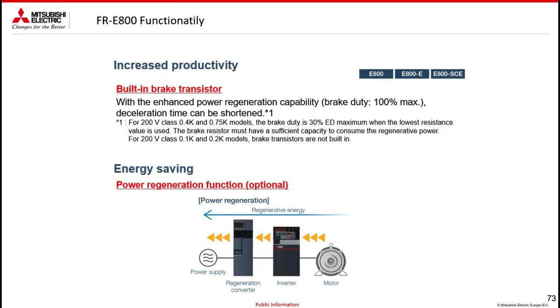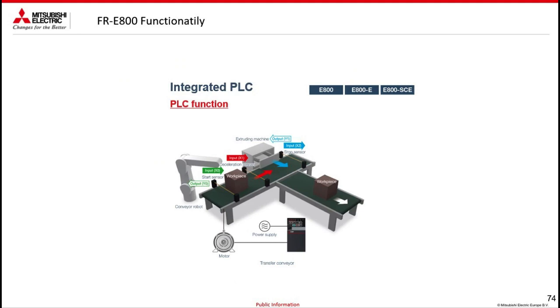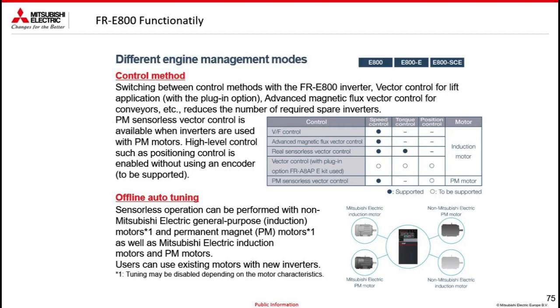We also have the possibility of managing the braking resistance, obviously already available, and the energy saving function. It also has an integrated PLC. It can be piloted in different control modes. In fact, it can be piloted with the classic V/F control mode or the advanced magnetic flux vector control mode, which is the open loop vector control of the FR-E700, so the predecessor. There is also the possibility of managing the encoder, which on the FR-E700 was not compatible. Now I can also manage the encoder and, as I said, the PM motor, the permanent magnetic motor. And this is not a small thing.